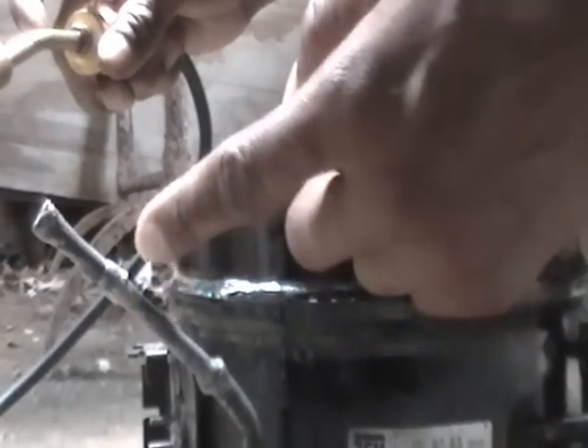In order to know if this is done completely well — if you can hear my nitrogen, it's escaping on the other side, which is the open end of this pipe. All I've got to do is plug here. This joint looks fairly well. I'm going to turn my manifold gauge off — that's my adjusting screw, my adjusting handle.